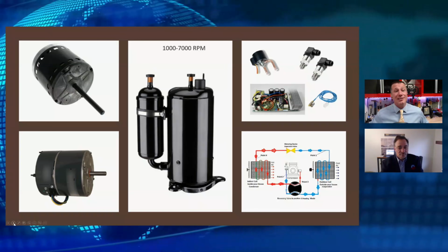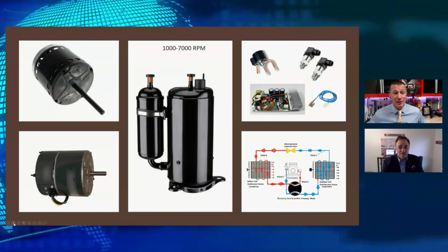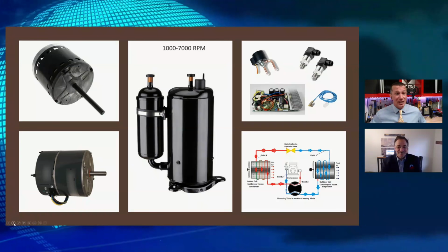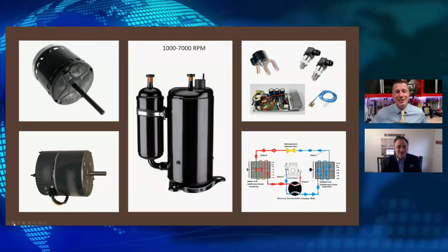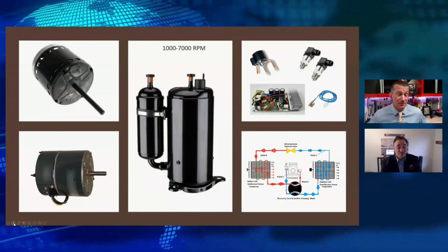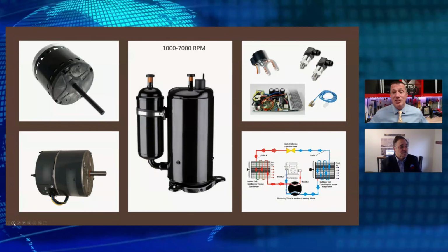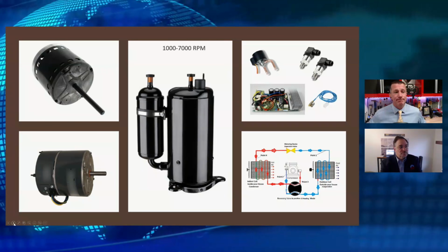That's going to be a shock to the installer or the service tech when they go out to work on this thing and they walk up to it and it's producing heat and it's just at 7,000 RPMs. That's a different sound when you're used to hearing a compressor chugging along at, say, 2,800 RPMs. So a significant change in the sound and the performance based on the components internally.